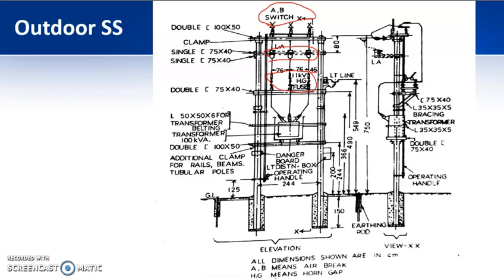So here you can see your transformer. This is nothing but your transformer. And this is a two-pole structure. We have said that on the two poles, you will be having the MS channels and a platform on which you are keeping your transformer. So the transformer is nothing but this one. Now, the 11 kV supply is coming to this air break switch, which is gang operated. And you can see that the lever of that particular air break switch is coming down like this till here, and then you're having your handle, and that is at 1.25 meters from the ground level. So this operating handle can be operated in order to open or close your air break switch.